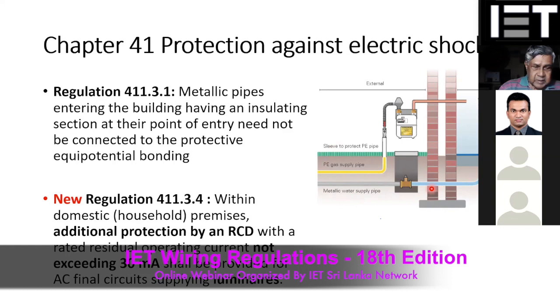And also there is another requirement for the luminaire. If you are supplying the light fittings for the building, then we have to protect them using an RCD where the I delta N should not exceed 30 milliampere. That is, its operating current should not exceed 30 milliampere. Sometimes you may experience issues, especially with LED and other things.